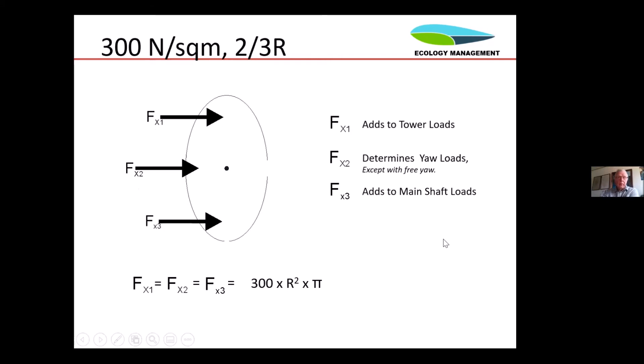Here is the 300 Newton per square meter rule shown more graphically. The force on top adds to the tower loads. The force in the middle adds to the yaw loads, except for free yaw — though free yaw brings other problems. The downward force adds to the main shaft bending. Those are the three points you should calculate the 300 Newton per square meter on, all at two-thirds radius out.